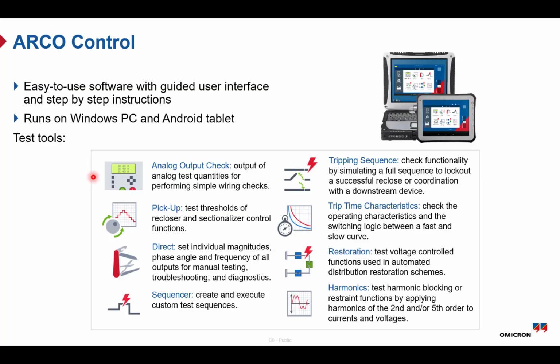The analog output check is used for basic wiring verification by injecting current and voltage signals. The pick-up tool is used to check protection thresholds, for example, when an overcurrent function starts to operate. The direct tool allows you to manually control outputs like current, voltage, phase angle, and frequency, which is useful for troubleshooting. The sequencer tool allows you to create a custom test sequence of up to 20 states for more advanced testing scenarios. The tripping sequence tool simulates full operation sequences like a successful reclose or lockout sequence, including trip, reclose, and lockout, to check the overall behavior.